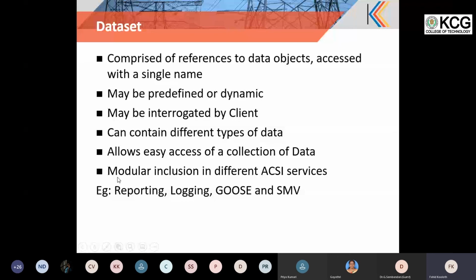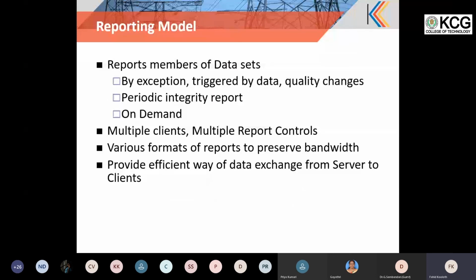Then another key thing is the report control block. This is one of the key things. So you have a grouping of data, that is the data set. Then this data set is associated with a report control block. Each report control block has a set of data, and this data can be reported based upon a data change, quality change, data update, or integrity, that is, a fixed time cyclic report, or on demand I can get the report. Then it can be given to multiple clients, and multiple report control blocks can be there in a server. This can be used to send data from server to client, especially from a bay to the station.